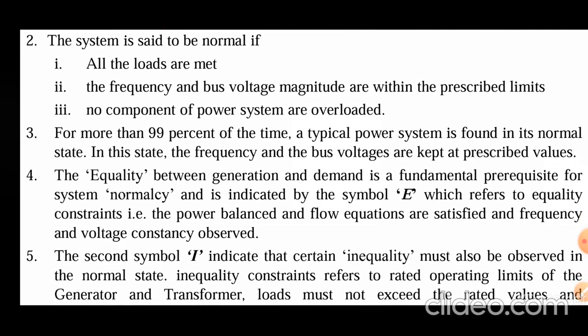For more than 99% of the time, a typical power system is found to be in normal state. In this state, as we have discussed, the frequency and bus voltage are kept at prescribed values. In the third topic, we discussed load frequency control. There we learned that system frequency should be kept near 50 Hertz, with a variation of plus or minus 0.5%. In a modern power system, we keep frequency at 50 Hertz and a tolerance of plus or minus 0.25% is prescribed.